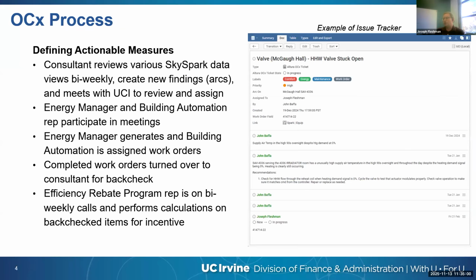So our process is really different than a retro commissioning, because a retro commissioning, typically you have maybe a 12 or 18 month project. You come in, you go into every single bit of the building, every room. You're really focusing on zone level, really detailed, actuator level items, and getting everything tuned up. And so you have construction associated with that, and a lot of extra programming that maybe wasn't present or wasn't optimized. In this case, instead, what we're doing is more of an iterative process.